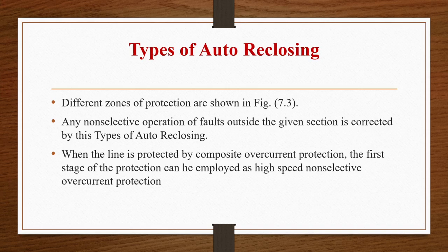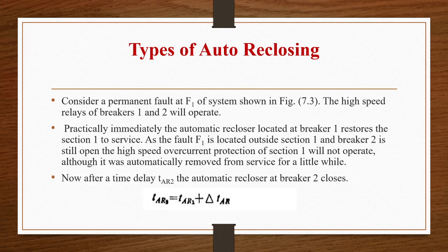When the line is protected by a composite overcurrent protection, the first stage of protection can be employed as high-speed non-selective overcurrent protection. So let us consider the figure where we have seen zone 1, zone 2, zone 3. There I have shown you a permanent fault at F1 of the system. Then high speed relays of breakers 1 and 2 will operate at that point. Practically immediately, the automatic recloser located at breaker 1 will restore section 1 to service. As the fault F1 is located outside section 1 and breaker 2 is still open, the high speed overcurrent protection of section 1 will not operate, although it was automatically removed from service for a little while.